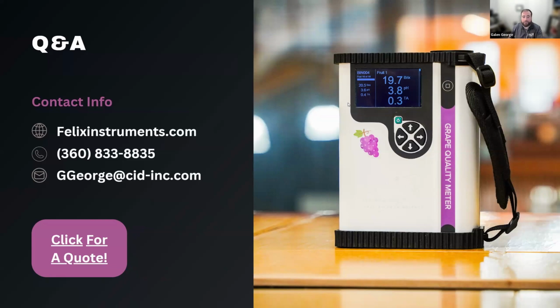The next question relates to that: maintenance and calibration required with intensive use, when, where, and how. The really nice thing is that performing the offset calibration is only a once-a-year thing. There's not a whole lot of maintenance, but I know how messy grapes can get from doing a lot of the lab work and analysis to create these models. The only thing you'll want to do is occasionally clean off the lens of your device if it gets too sticky and caked on with grape juice. A microfiber cloth comes with it, or you can use a gentle cleaning solution and a Kim wipe or some kind of non-scratching material to wipe off the lens.